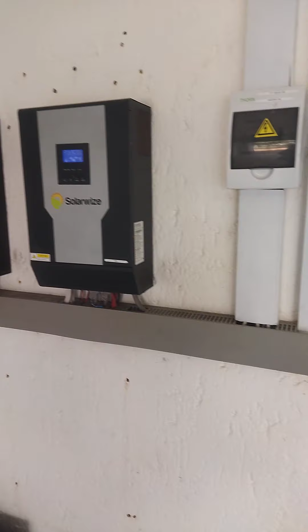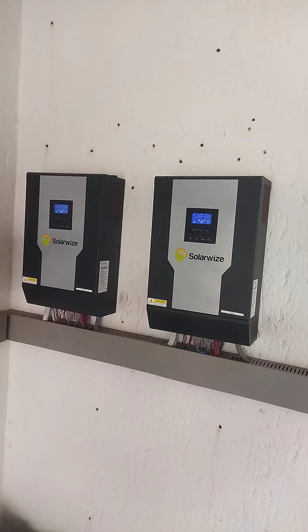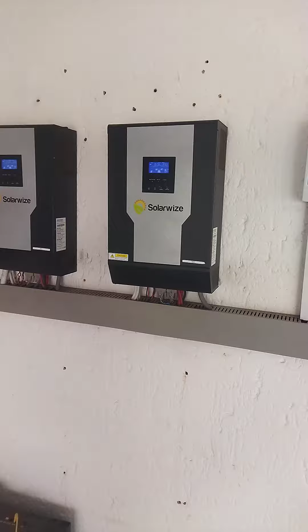The challenge we've been having with the installation is that it would not accept generator power. There is a 40 kVA generator on the property. Due to frequency issues, the moment the frequency of the generator goes up or down, the inverters won't accept that power and they shut down. So we've had to integrate a mechanical system that would assist.